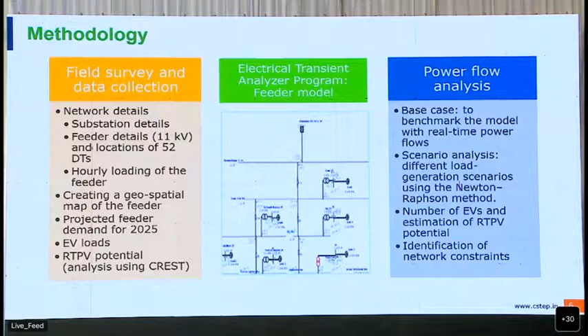And we did power flow analysis. At first, we benchmarked the analysis based on the existing loading pattern of the feeder. That means either loads at DTs or the loading of the entire feeder have been verified and weighted based on the real-time power flows for that particular instant. This load has been enhanced for 2025, and also the EVs and the RTPVs have been considered for 2025 scenarios that we will see in the next coming slide.